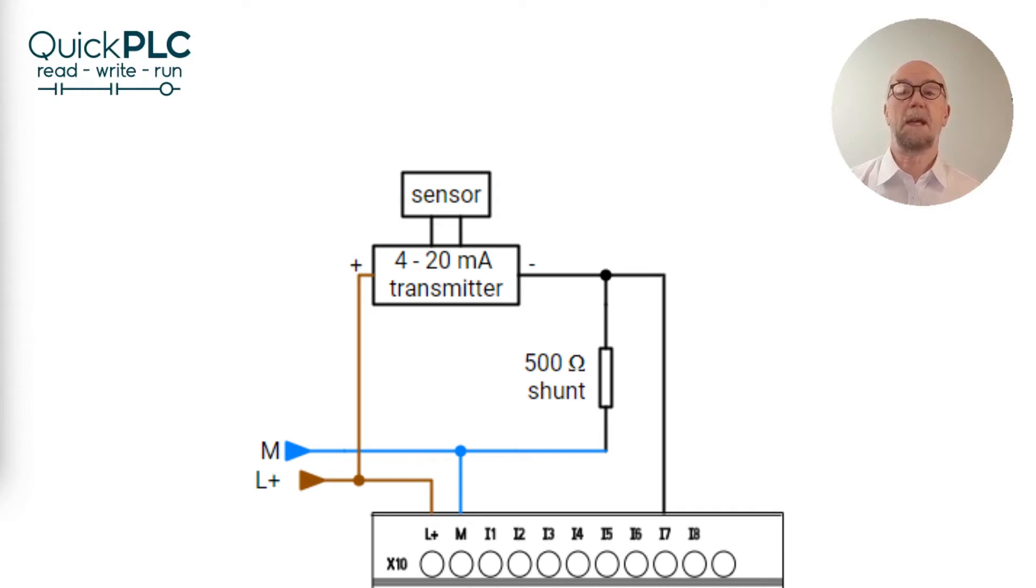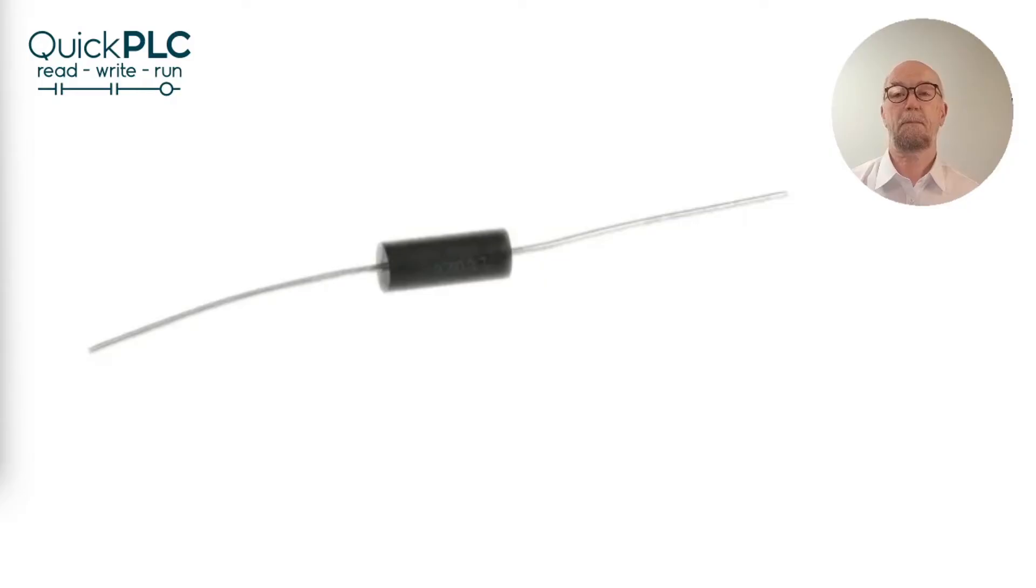Note that four milliamps into 500 ohms will give us two volts minimum. So our internal digital reading will be in the range of 200 to 1000. Various companies make a 500 ohm 0.1% tolerance high stability resistor suitable for this application. And they cost only a few euro which is a lot less than the cost of an analog input module.